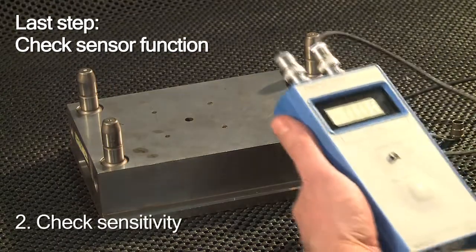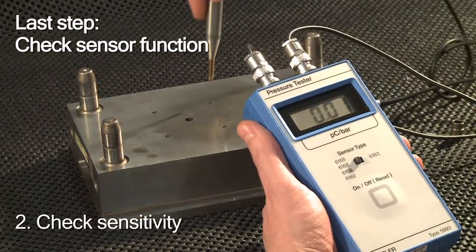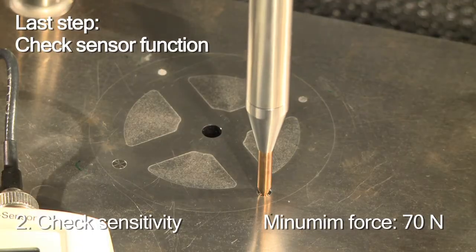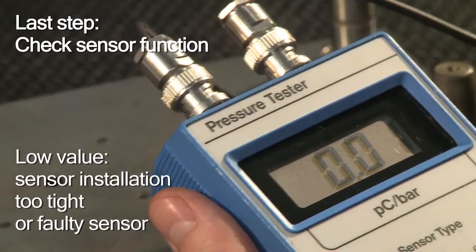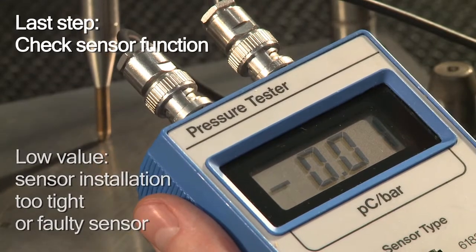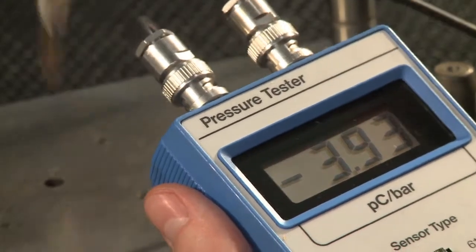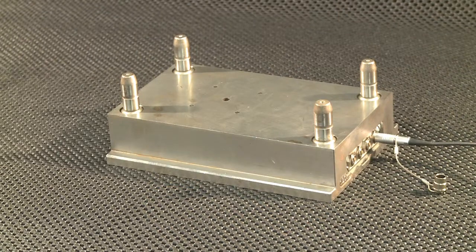Finally you check the sensor's sensitivity. If the indicated value is too low, the sensor is either installed too tightly or it's faulty. If it consistently stays within the recommended range, everything is fine. Congratulations.